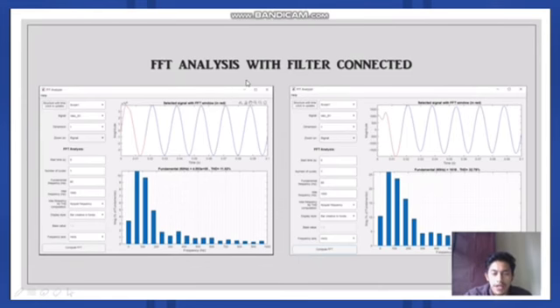After the filter is connected in the equivalent circuit, it shows the waveform for the voltage and the current become stable, and it shows a perfect sinusoidal waveform for current and voltage here. So the total harmonic distortion at this stage is 11.52%. It decreased from 13.8% before it was connected with the filter. The total harmonic distortion for the current when the filter is connected is 32.79%.